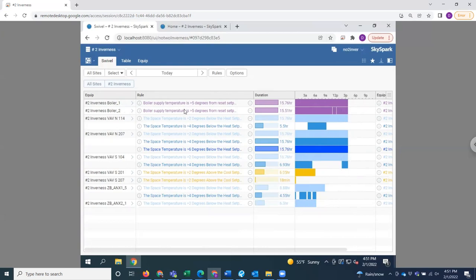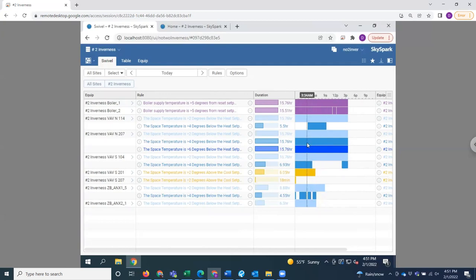So looking at this equipment, we've got a repeat offender with a pretty substantial temperature gradient or deviation from our heating set point. It's greater than six degrees in our VAV north 207. That's a specific zone that is substantially colder than it is supposed to be and it has been that way all day.